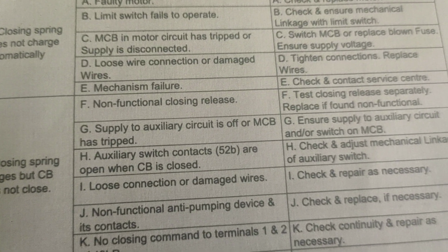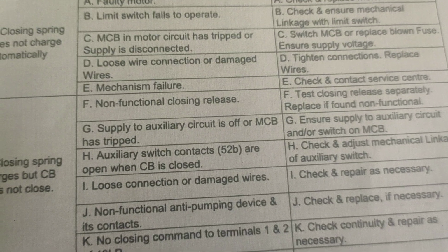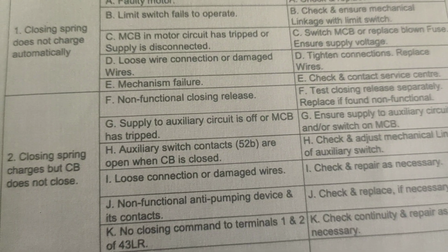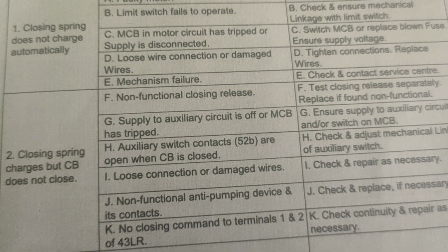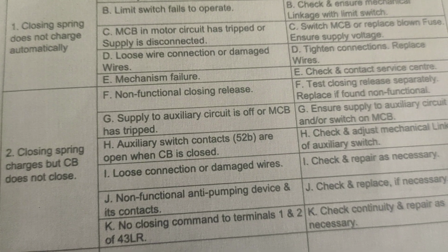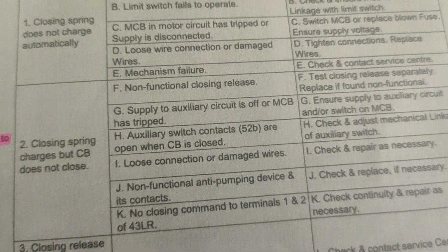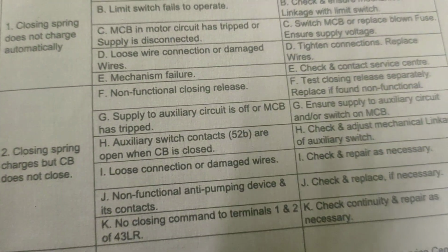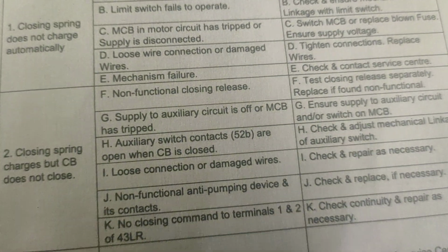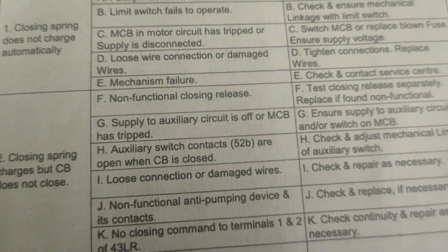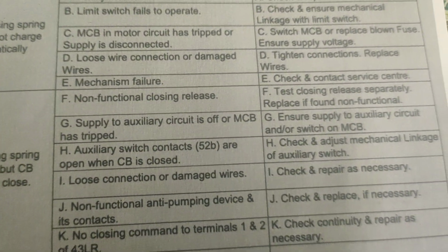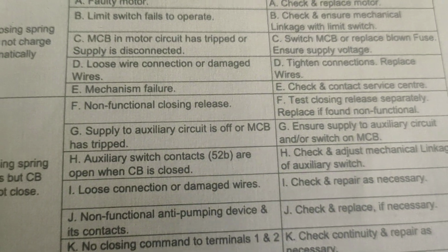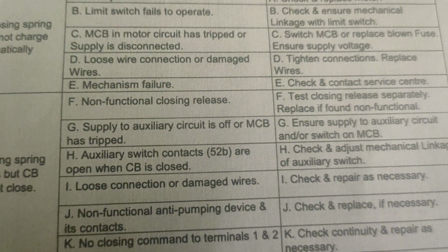52A is very important. If the 52A is not in the open condition, the circuit breaker is closed. So the auxiliary switch contacts 52A are open when the circuit breaker is closed. Check and adjust the mechanical linkage of the auxiliary switches.